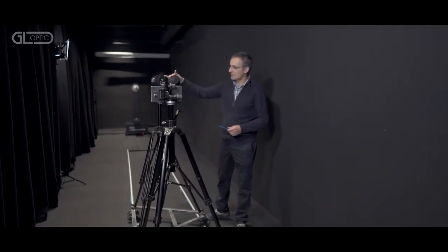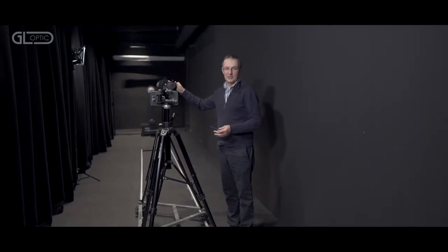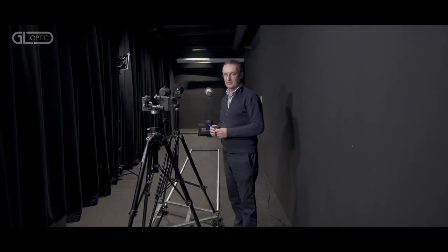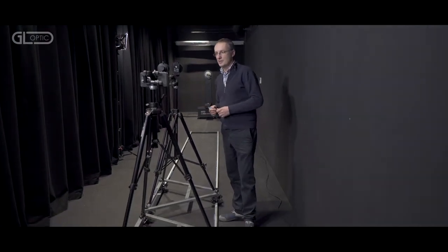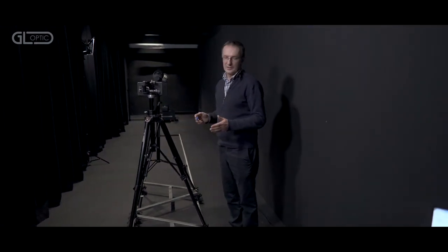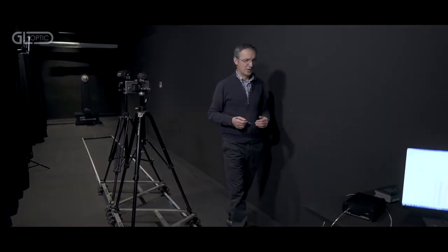So we have either a radiometer, which is calibrated and set for a very narrow band of UVC, in this case the 254 nanometer mercury line, or the spectroradiometer, which is sensitive in a wider range and covers the UV range completely from 200 nanometers to visible light.